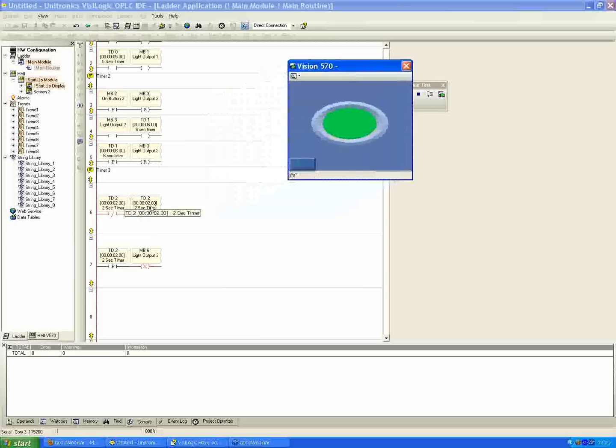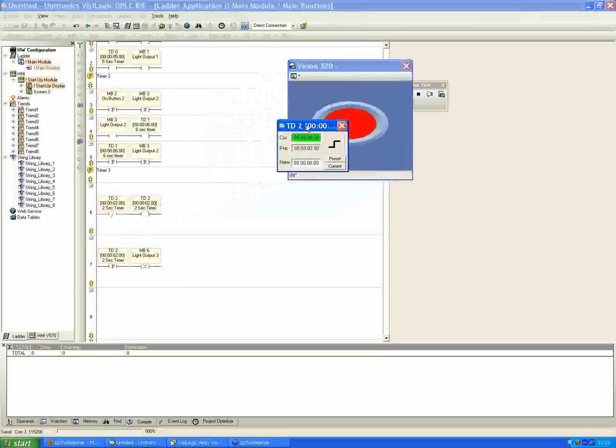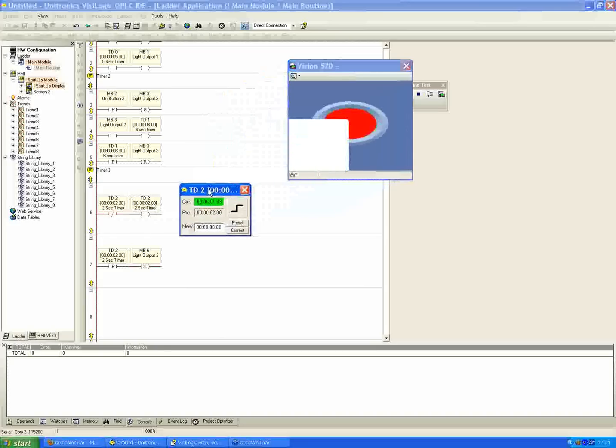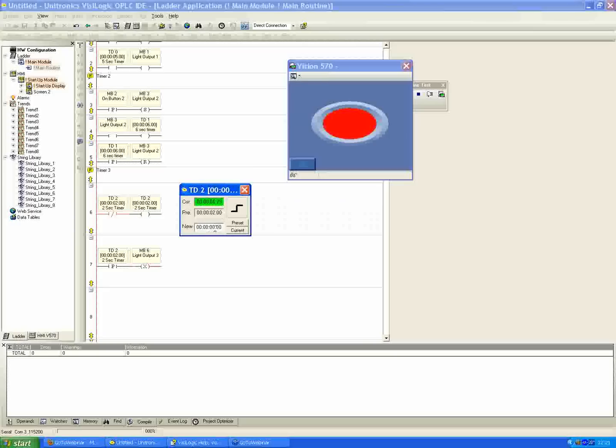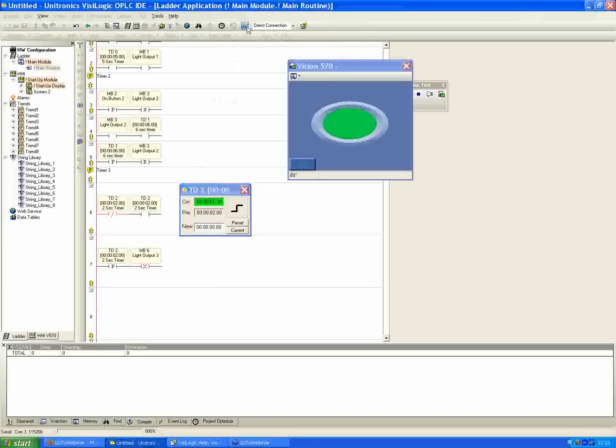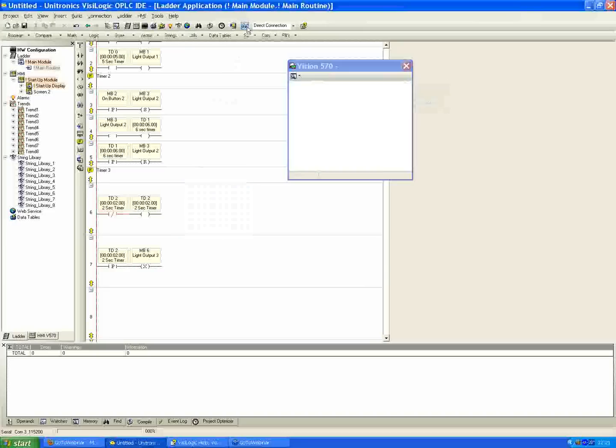If you ever click on anywhere where it says TD, whatever, whether it's a coil or a contact, when you click the yellow portion above, it will open up the timer window, which in this case we could see it's just continuously counting down from two seconds. The current time is in green. You can see the preset stays at two seconds. This is where you can also enter in a new value for the timer as well if you wanted to. You can do it right from online test mode. But somebody also asked about changing that from the HMI.